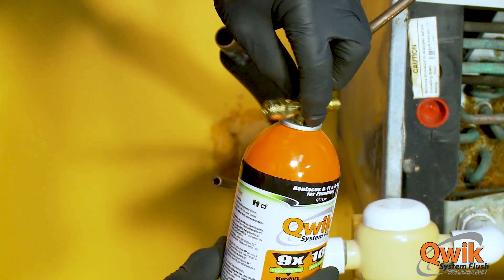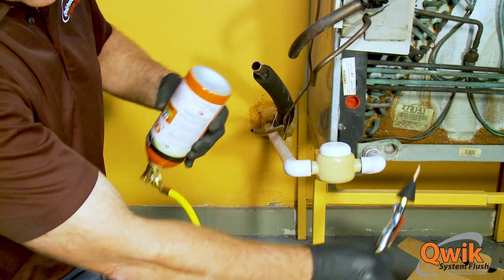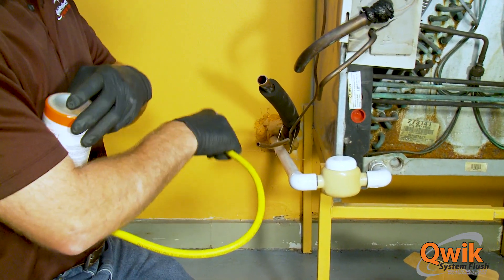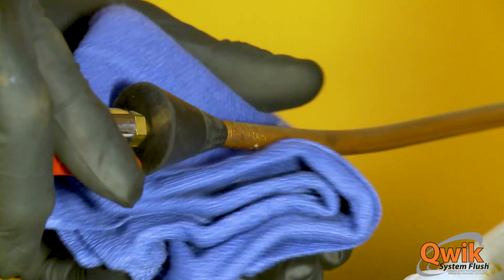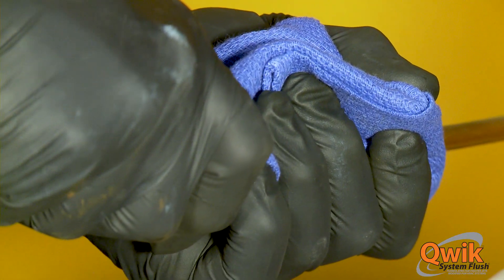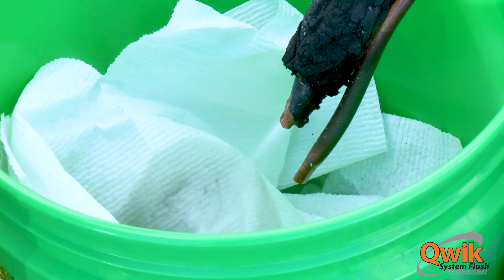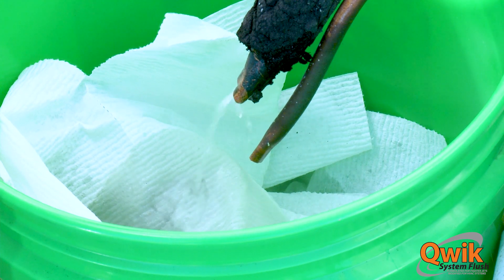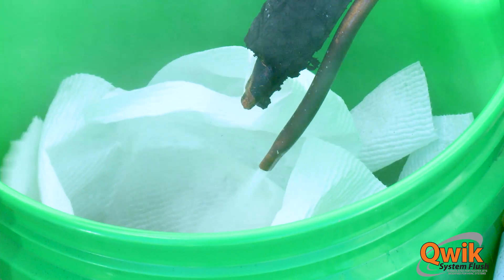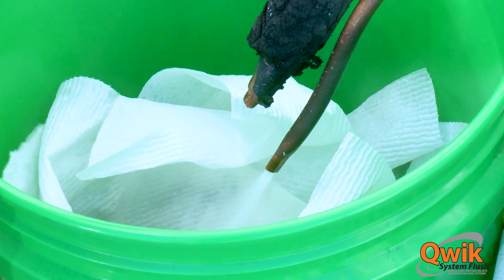Now, introduce Qwik System Flush into the line sets. The can must be inverted for proper liquid flushing. If a Schrader valve is unavailable at the opening you would intend to flush, simply use Mainstream's line set flush tool. Repeat a 150 psi nitrogen purge in all areas where Qwik System Flush was introduced to the line set. Continue to purge with nitrogen for at least a minute after no liquid or waste can be seen exiting the line. Make sure you have a container in place to catch flushed waste.